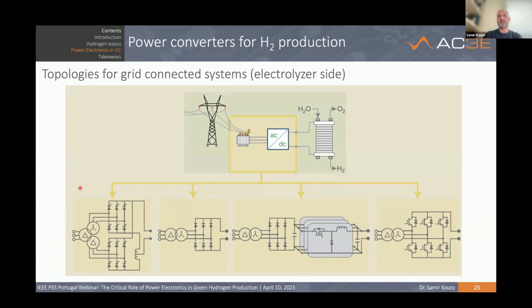And a typical converter used is the thyristor-based rectifier. So in this case it is a 12-pulse thyristor-based rectifier. And you can also find more pulses as well, 18 and 24 and so forth. All of them with the secondaries in parallel to increase current, right? But of course, these have very poor power quality at the grid side. So here you end up using filters, unless you use transformers that have a lot of pulses, like over 24 pulses.